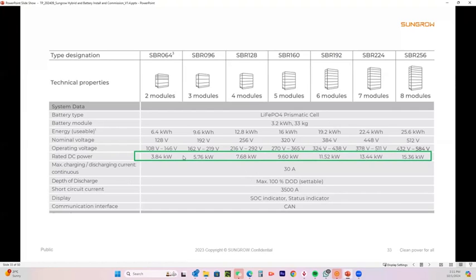This is the rated DC power, okay? So that's the maximum power that's going to come out of a battery stack. Now this is the important one. For example, if somebody installs a 10 kilowatt hybrid, an SH10RS, and they want 10 kilowatts on the backup, right? If you sell them 3 modules, the maximum out of that is 5.76. So you're not going to get 10 kilowatts at all. You're only going to get 5.76 kilowatts out of there.